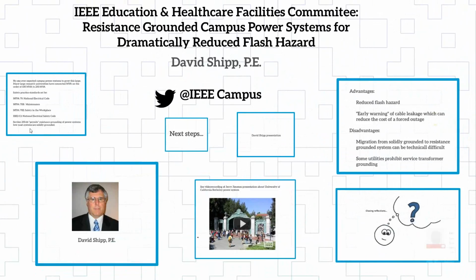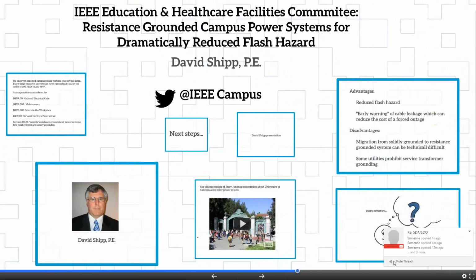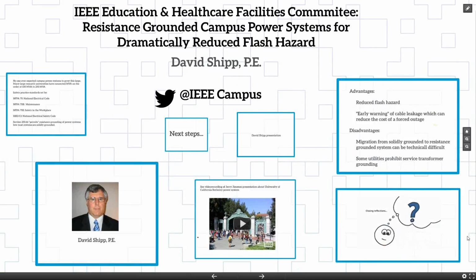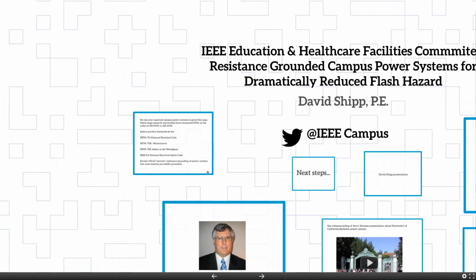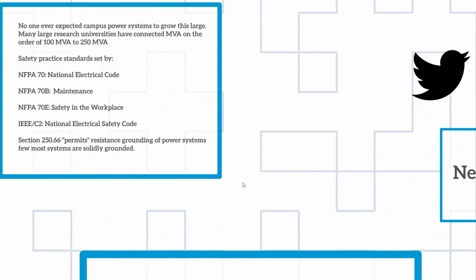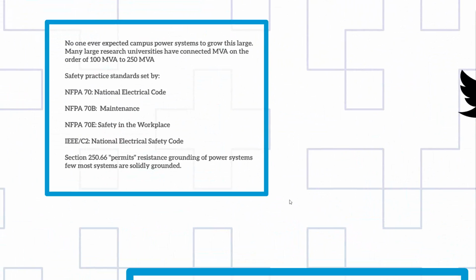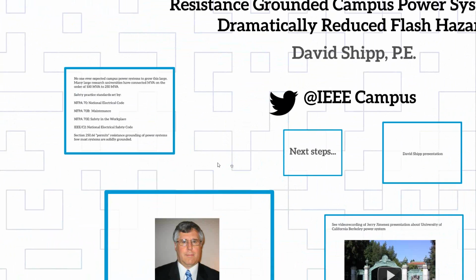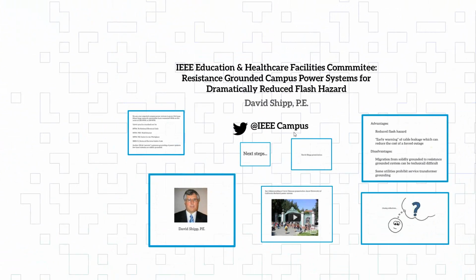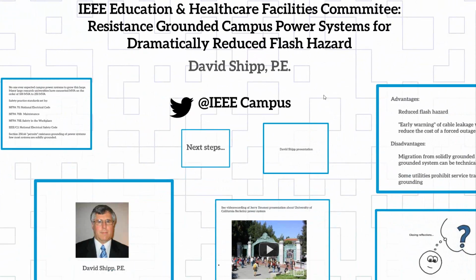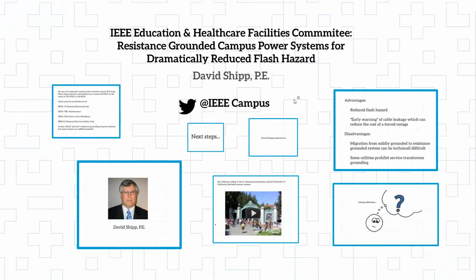So what I want to do is improve the safety. Now, there's only one national code requirement that differs when I go to high resistance grounding versus the other. Well, I say there's three. If you go to the high impedance grounded part of the code, first of all, service continuity or something like that is a requirement or desirable. You cannot serve line to neutral loads, and you must have trained maintenance personnel.